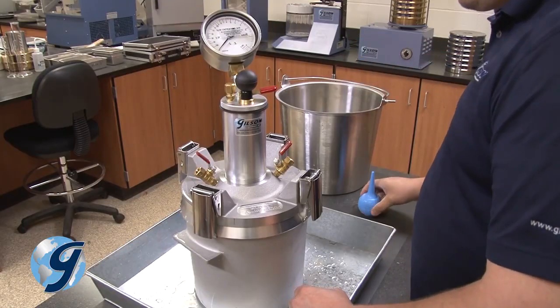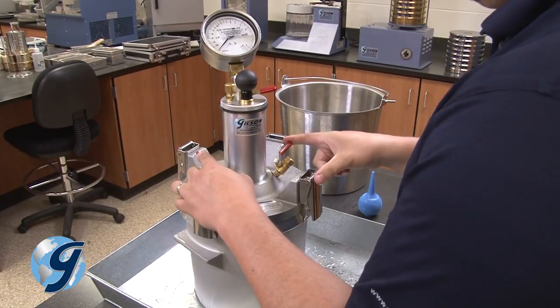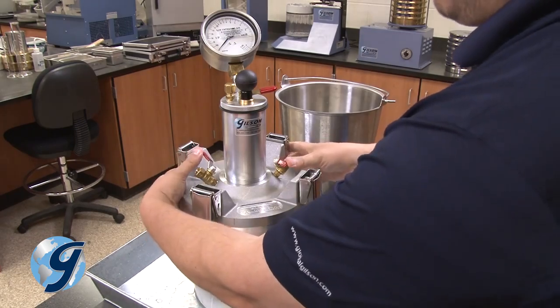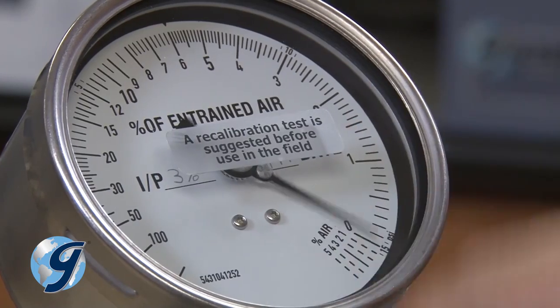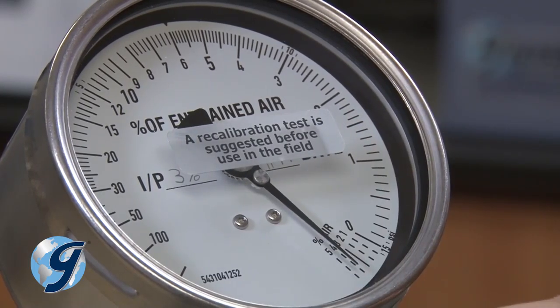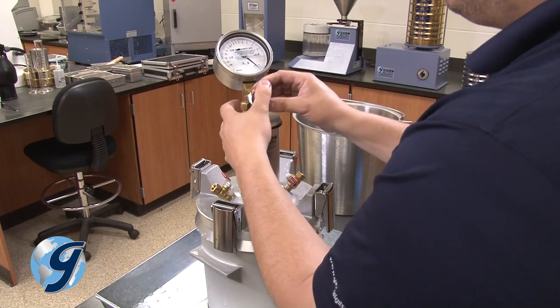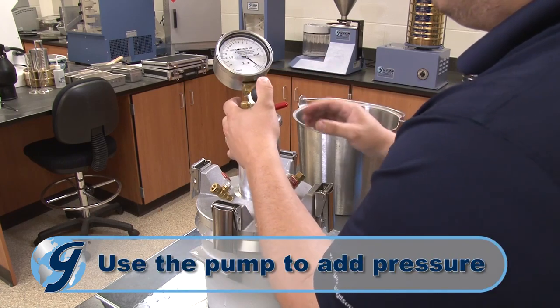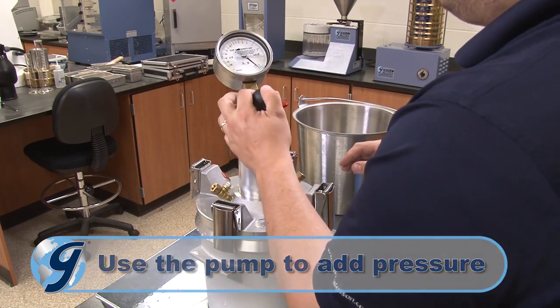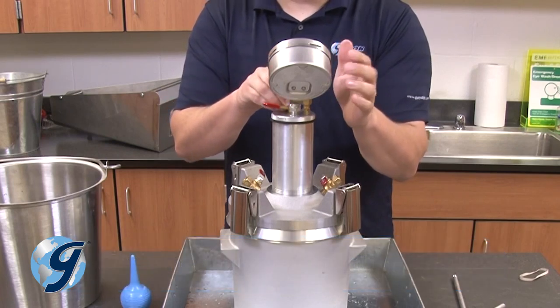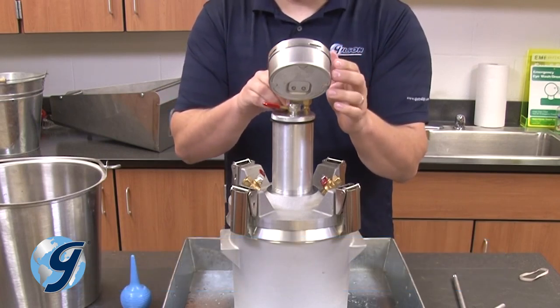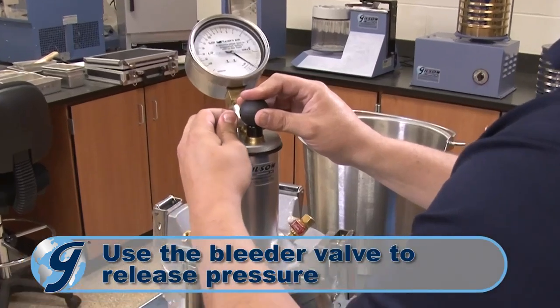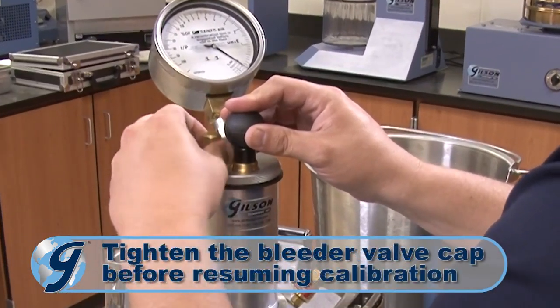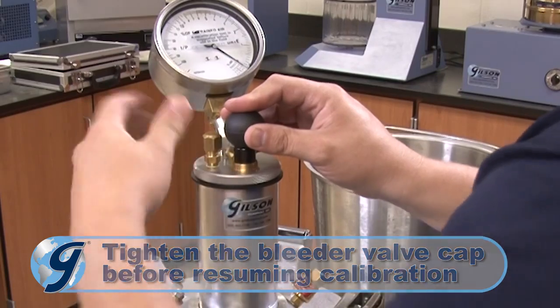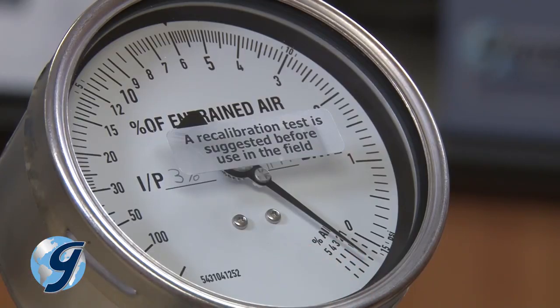Once you're sure the air has been removed and the base is full of water, close both petcocks and pump the unit up until the dial comes around to the predetermined initial pressure reading, visible at approximately the 5 o'clock position. Next, make small adjustments to assure that the needle is aligned to the predetermined initial pressure mark by lightly tapping the gauge body to stabilize the needle. And if too much air is pumped into the meter, loosen the air bleeder valve cap to reduce the pressure. And be sure to tighten the valve cap before resuming.